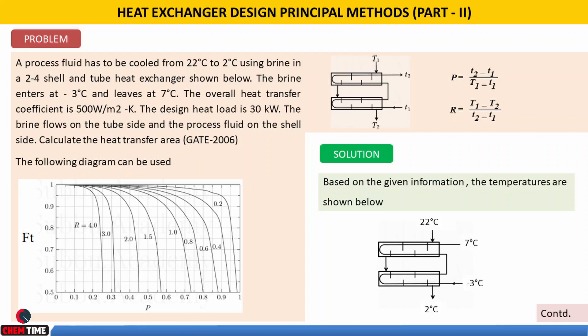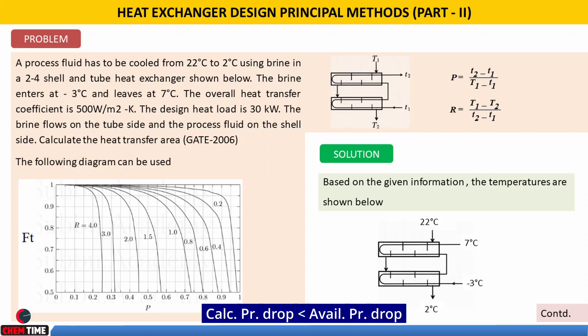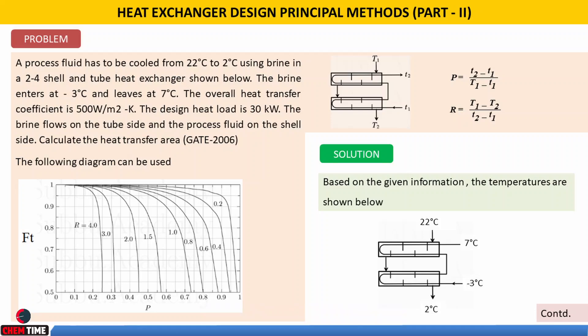Now coming to the problem — first and foremost, why do we go for a 2-4 shell and tube, 2-pass configuration? This is required if the calculated pressure drop is less than the available pressure drop. We go for multi-pass to increase the heat transfer coefficient and to effectively utilize the available pressure drop.